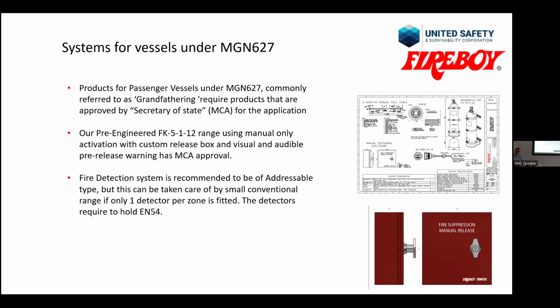You should then count down 20 seconds before pulling the handle, and the display unit will then alarm them, let them know that the discharge has happened, or that you have a fault, and it will also alarm if you have a low pressure switch. Because this is manual only discharge, you have to have a fire detection fitted as well. Minimum requirement is for fire detection in a machinery space. So you could just fit a single detector. You could fit one of the 2-zone panels, which allows you to monitor then your passenger area and your machinery space. The requirement for the system, unfortunately, is that it has to be addressable, because they want to know exactly which section has gone off in alarm.